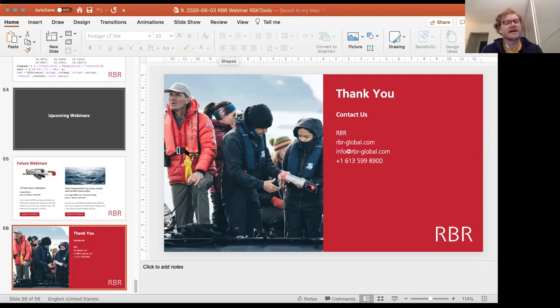Or I recall we talked to Greg Johnson about it a little bit, and he said one thing you can do is just zero all the calibration coefficients in Ruskin, and then recompute the data, and then you'll effectively have a voltage ratio. Okay, Sarah, let us know how that works. RSKtools doesn't do that. You could make a function that does it. We don't have one right now.